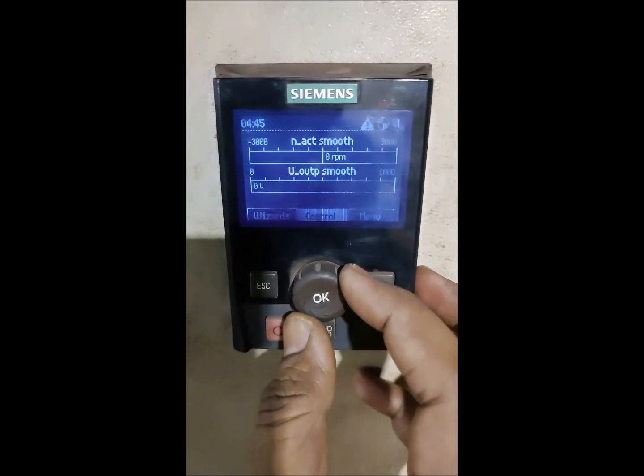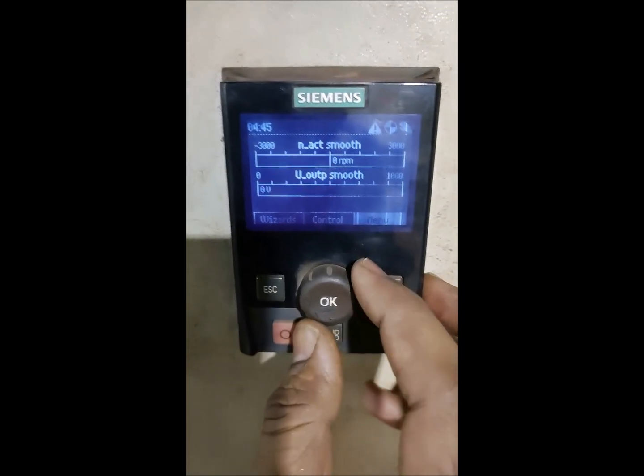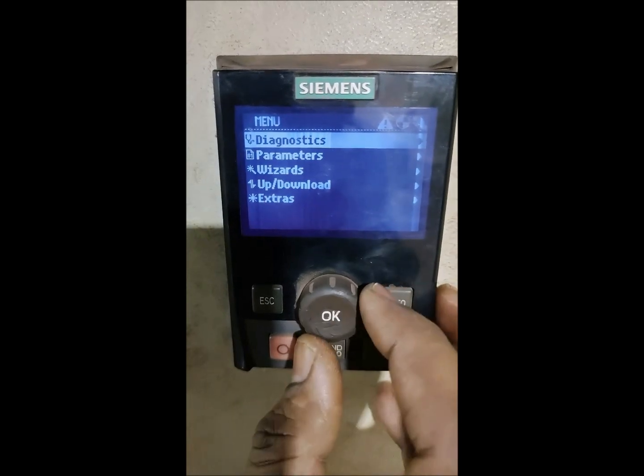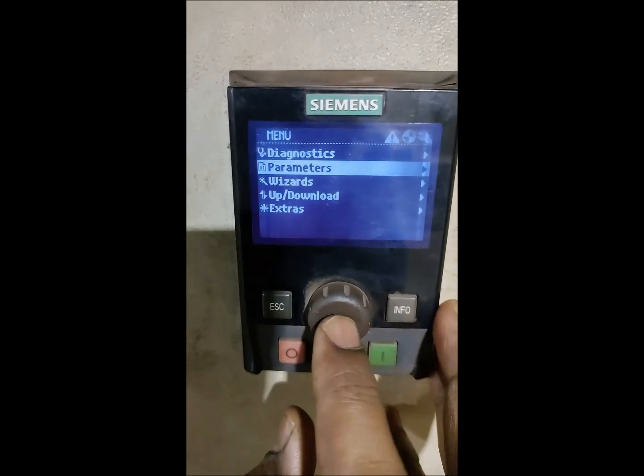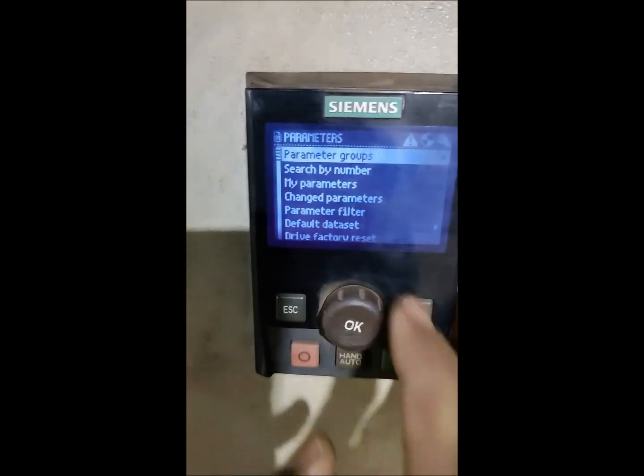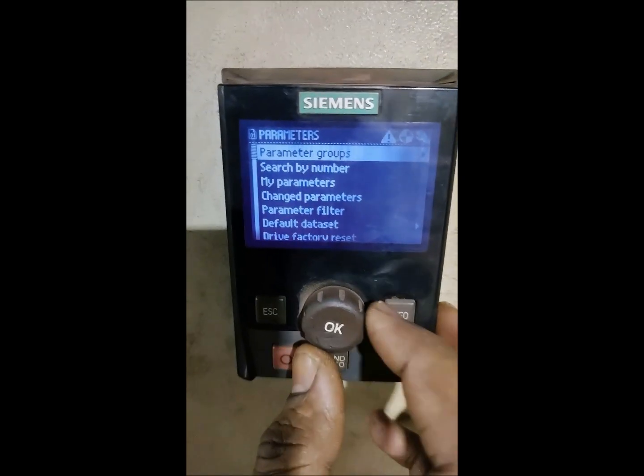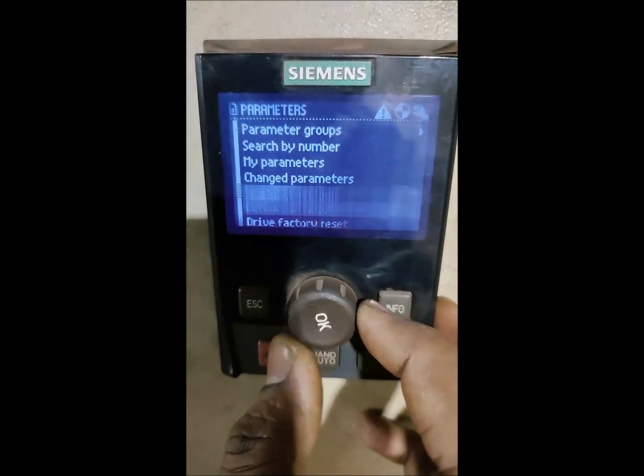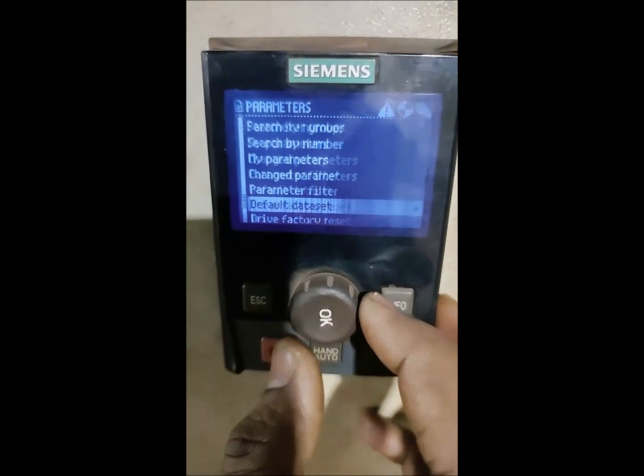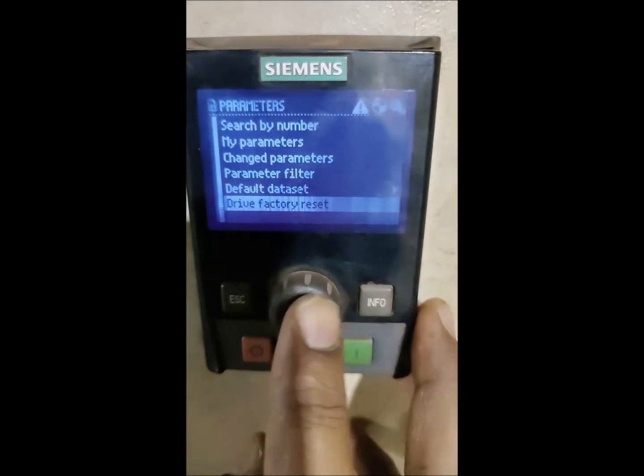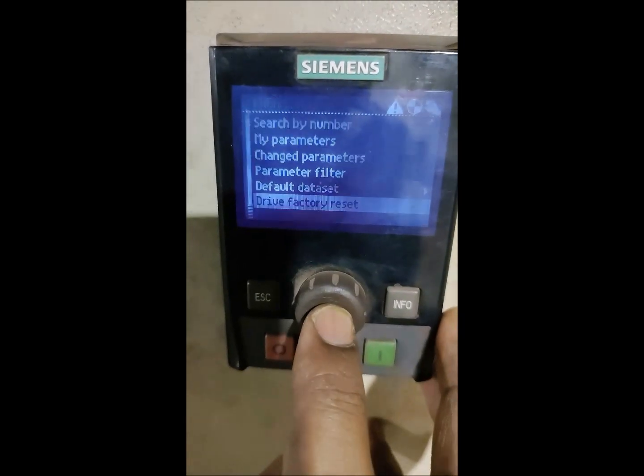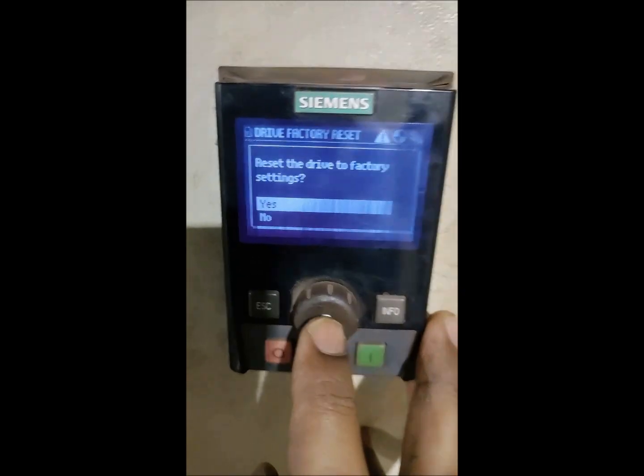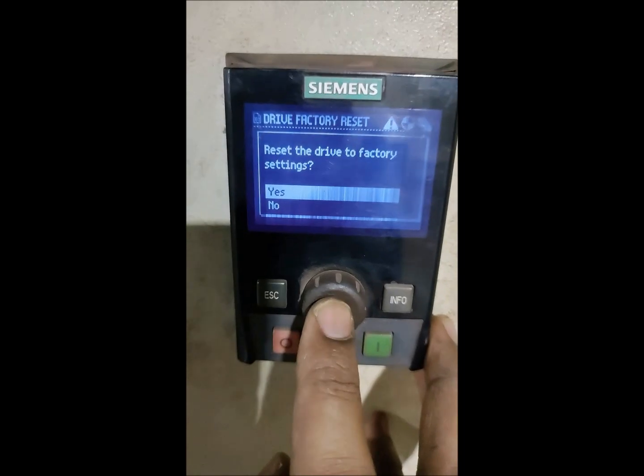This is the faulty drive which needs to be fixed and first we'll do the factory reset. On the right-hand side is the menu. We'll go to parameters, and at the bottom there is 'Drive Factory Reset'. This option here you can see. We'll select it and press the button, and it will ask 'Reset the drive?' - just press yes.